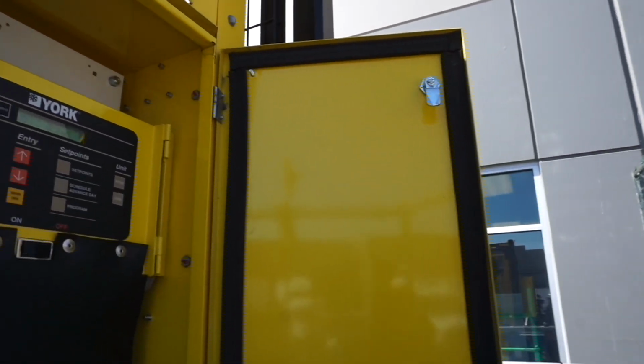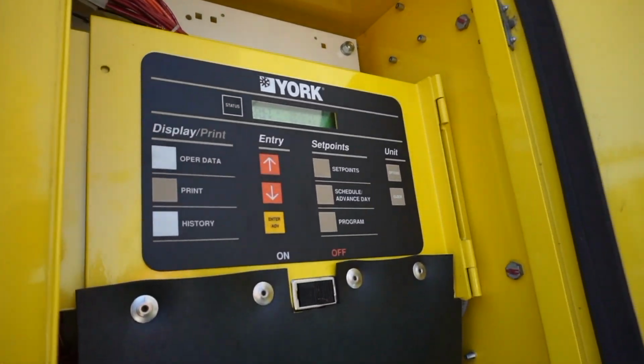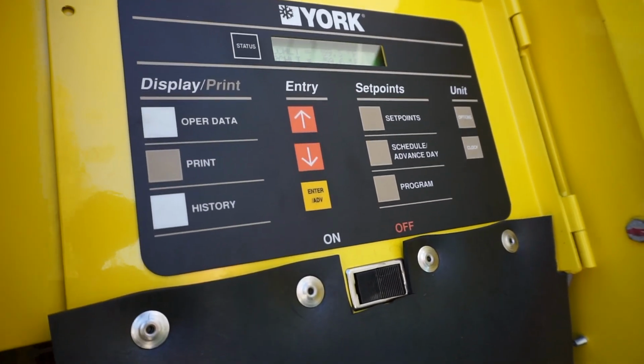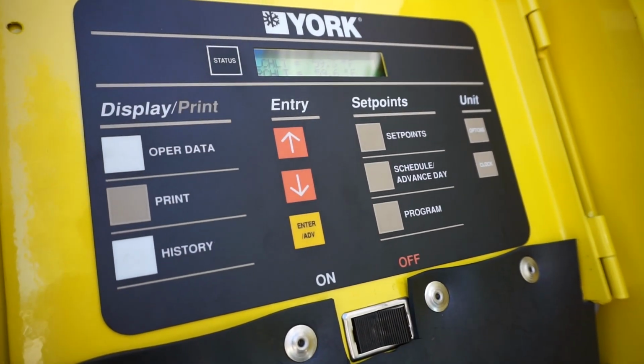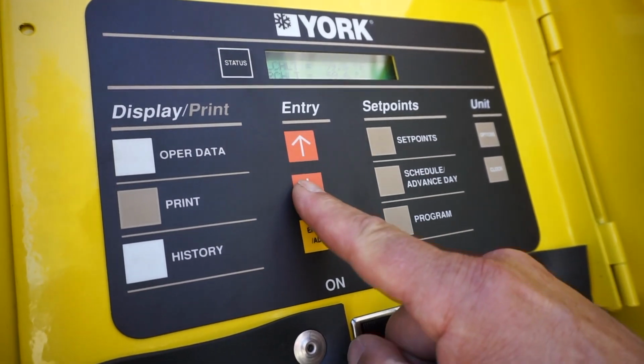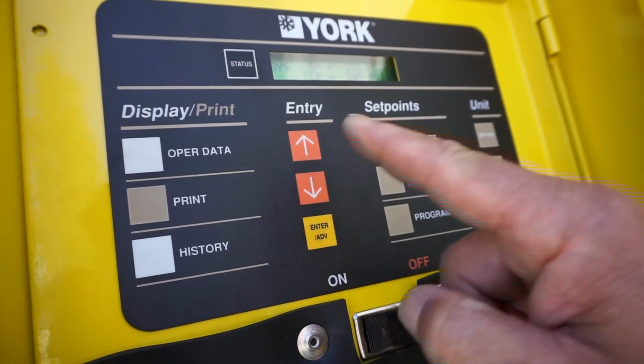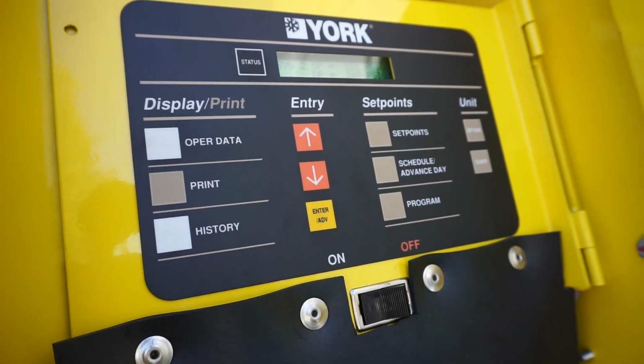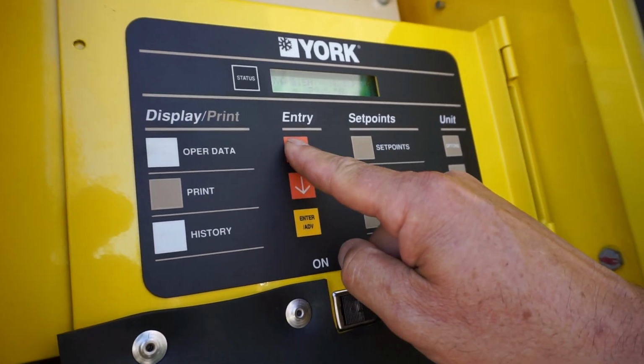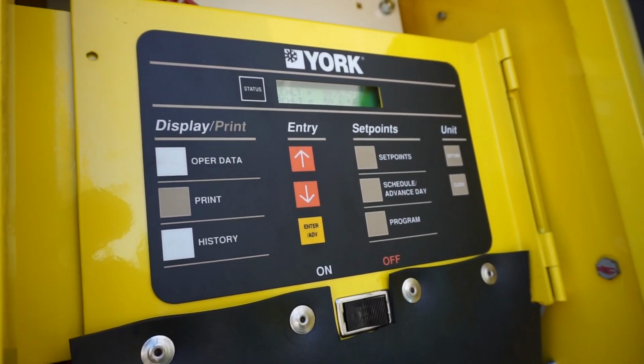The brains of this chiller is all controlled through this programmable York control. We take the set points that our customer is looking for - their return water temperature, their leaving water temperature, and their flow rates. We enter them into our system, then the unit monitors them and comes on and off accordingly so that we are providing the temperature of water that our customer is after.